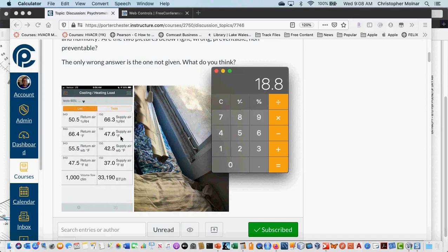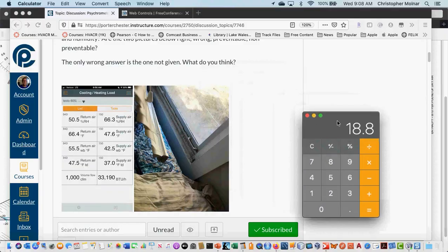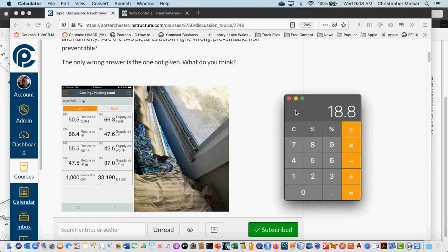So our return air minus our supply air, I come up with 18.8. Usually we go for about 15 as our magic number there. So the temperature split between return air and supply is usually about 15, can be less. It's not normally more, so this is a little high.